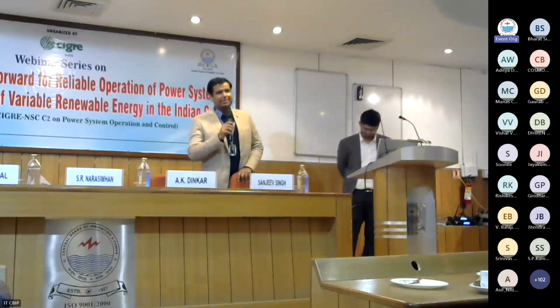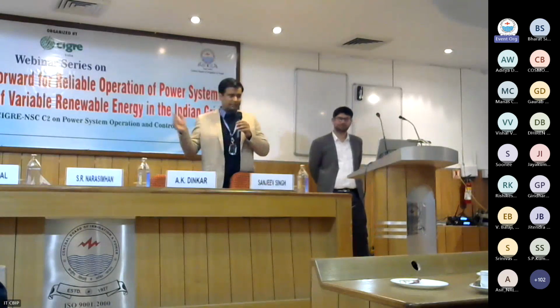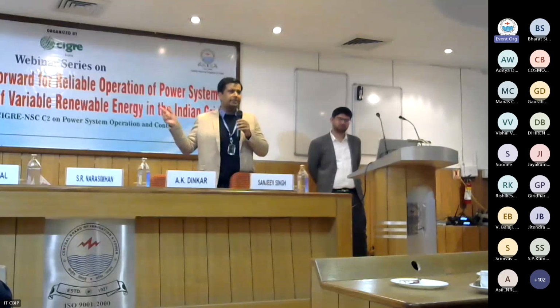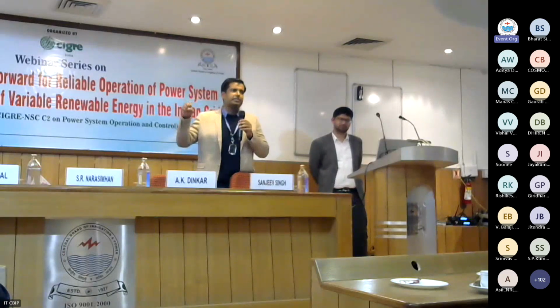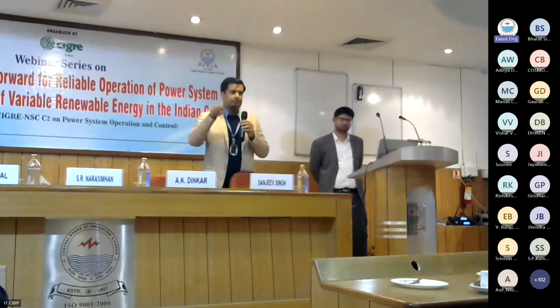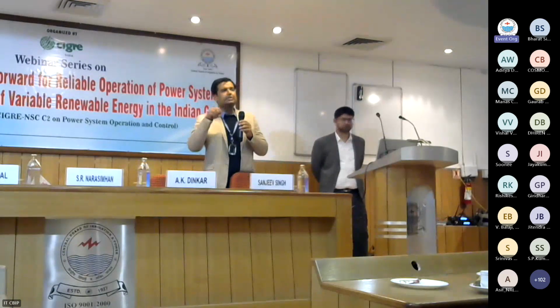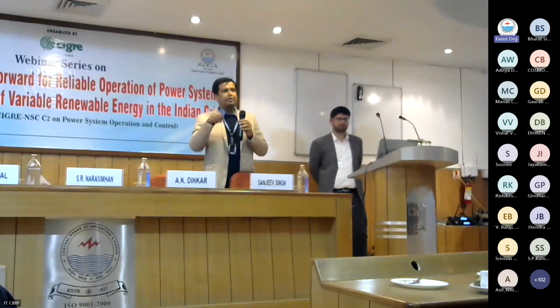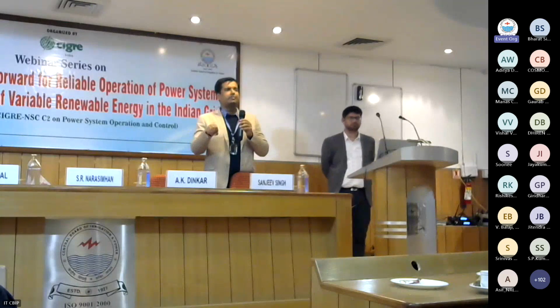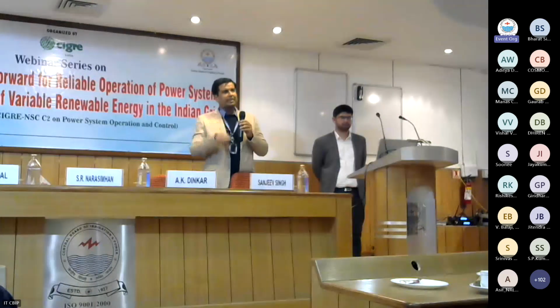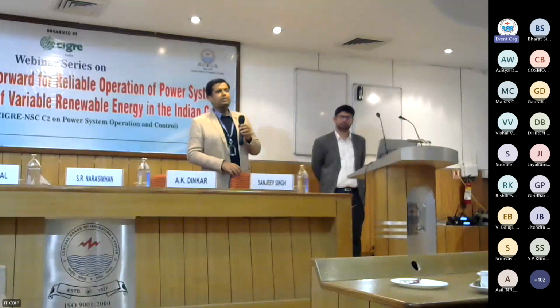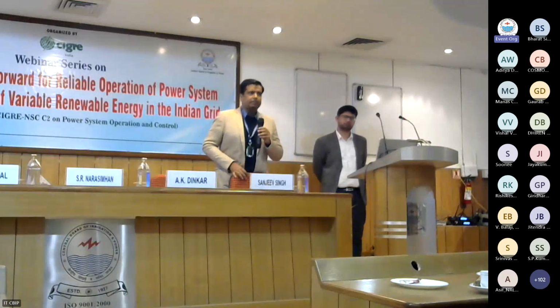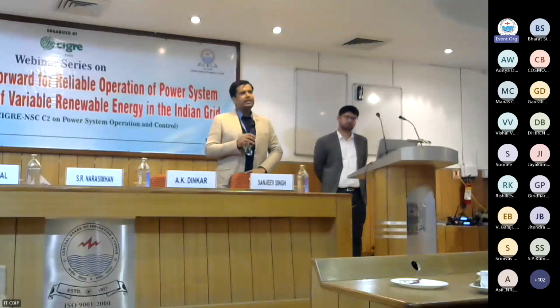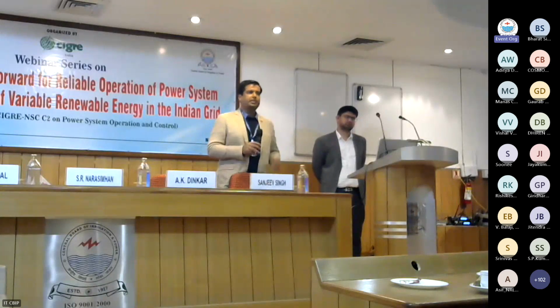Plants do have power quality meters and power quality analyzers. As we showed in our slides also, the power park controller's data fetching equipment, which fetches the real-time voltage and real-time reactive power from the point of interconnection or the high voltage side of the RE plant, is the power quality meter. Certainly those have very good archival facilities and harmonics can be seen. So they are there, power quality meters, and certainly as per the CEA requirements, everyone has to comply with that.